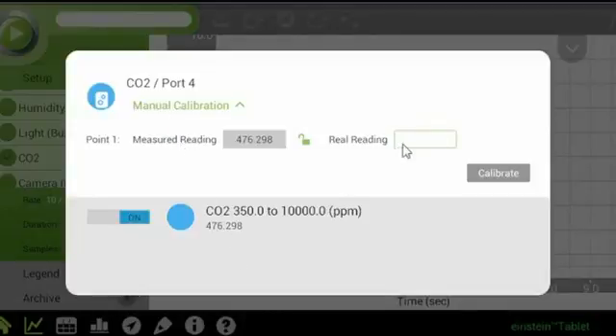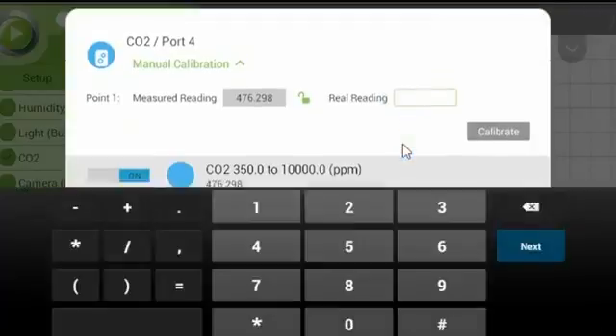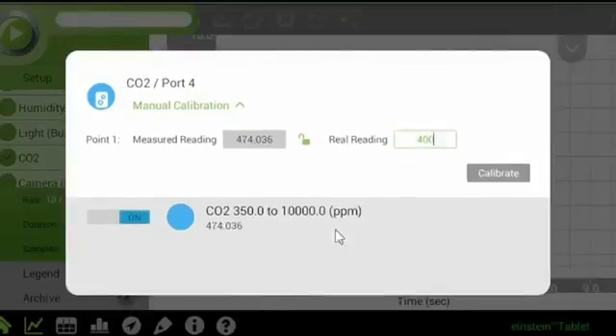We know that our atmosphere contains about 400 parts per million of carbon dioxide, so enter 400 in the real reading box. Wait for the reading to stabilize, and then tap the lock button. Tap Calibrate. Close the calibration box by tapping outside it. The sensor is now calibrated.